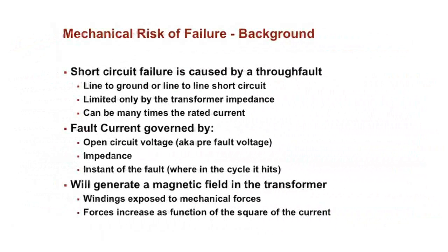Okay, so mechanical risk of failure. Usually a short circuit failure is caused by some kind of through fault. This can be a line-to-ground fault or a line-to-line fault, coming back to the transformer. And when this happens, the only thing that limits it is the transformer impedance. So a transformer that has lower impedance has to sustain much higher mechanical forces than a high impedance transformer. And the short circuit current can be many times the normal rated current.